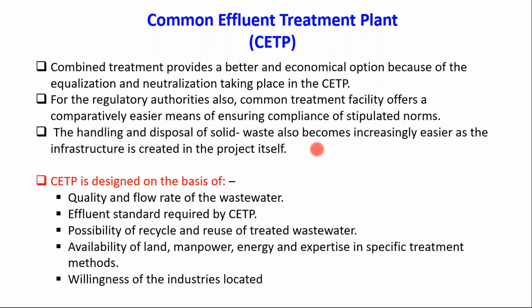Regulatory authorities are satisfied with these norms and facilities. The handling and disposal of solid waste also become increasingly easier as the infrastructure is created within the project itself, so at the same site we can treat both effluent and solid waste. CETP is designed on the basis of quality and flow rate of wastewater, effluent standards required, and the possibility of recycle and reuse of treated wastewater.